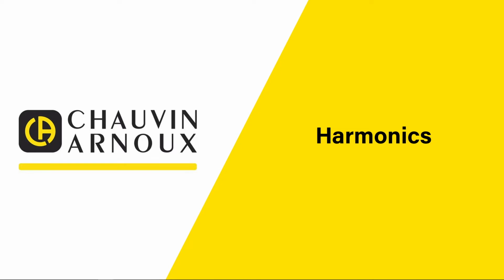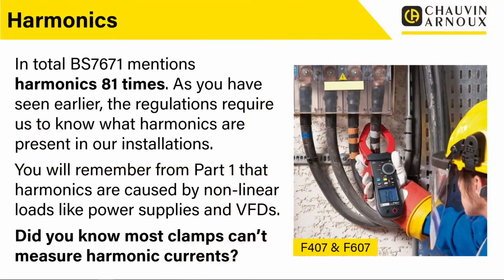So in this section, we're going to have a look at what the reg says about harmonics. In total, BS7671 mentions harmonics 81 times. As you've seen earlier, the regulations require us to know what harmonics are present in our installations. You'll remember from part 1 that harmonics are caused by non-linear loads like power supplies and variable frequency drives. But did you know that most clamps can't measure harmonic currents?